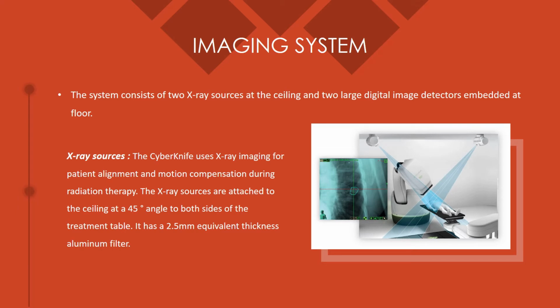Imaging system. The Cyberknife locates its target by comparing the images from the treatment planning system to the images taken of the patient before and during the treatment. These treatment images are taken with an integrated X-ray imaging system. The system consists of 2 X-ray sources at the ceiling and 2 large digital image detectors embedded in the floor. The Cyberknife system utilizes live image guidance, and if the patient or the target moves during the treatment session, this will be detected and corrected by changing the direction of the robot or moving the robotic couch on which the patient lies.